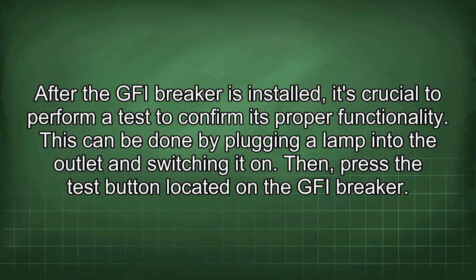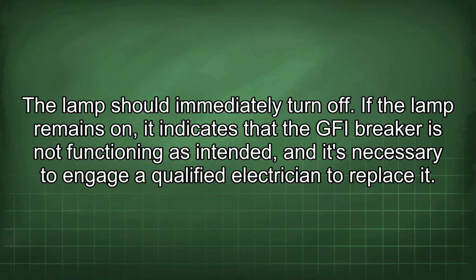This can be done by plugging a lamp into the outlet and switching it on. Then press the test button located on the GFI breaker. The lamp should immediately turn off. If the lamp remains on, it indicates that the GFI breaker is not functioning as intended and it's necessary to engage a qualified electrician to replace it.